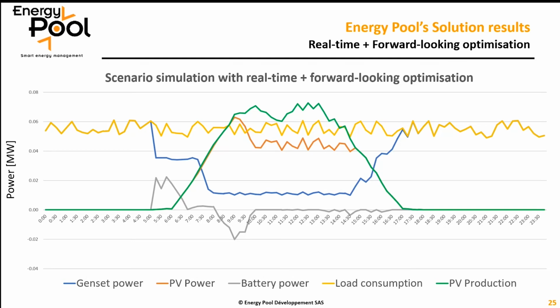After this, please click, Jean-Pierre. We can shut off the third genset, and then the PV production will start, and we will use PV. That's exactly what happened. At 6 a.m., PV starts to produce, and once more at 8 a.m., the PV production is more important than 80% of the load. But since the battery is empty, we can use the battery to avoid curtailment of the PV.